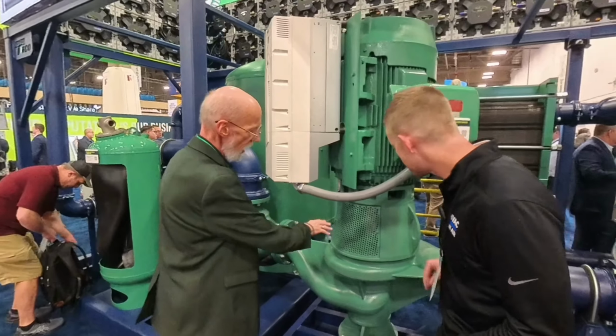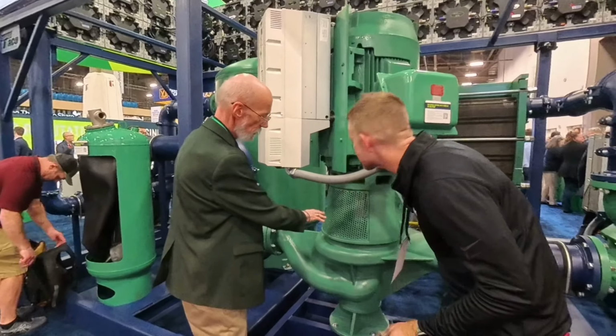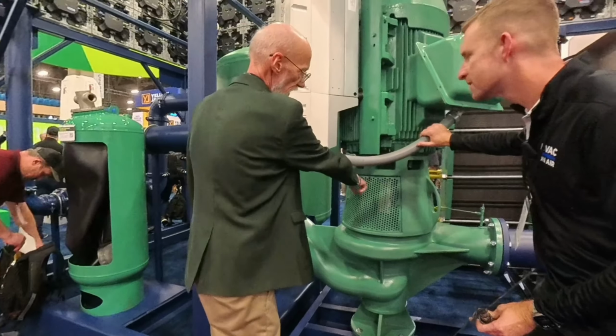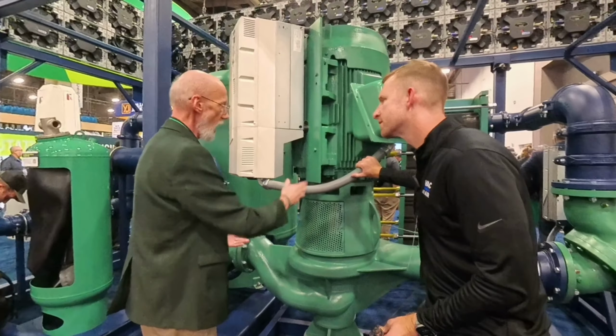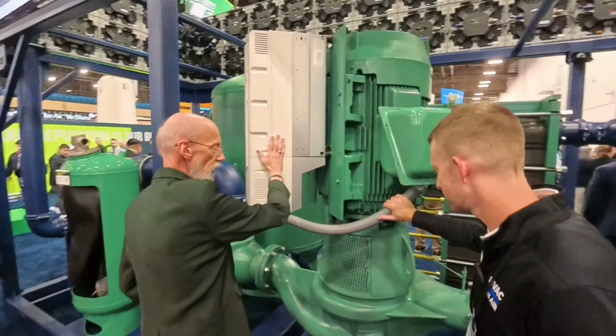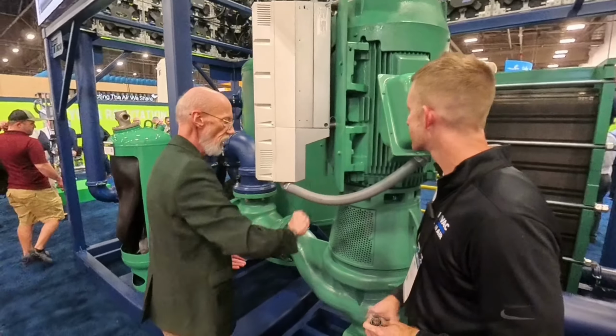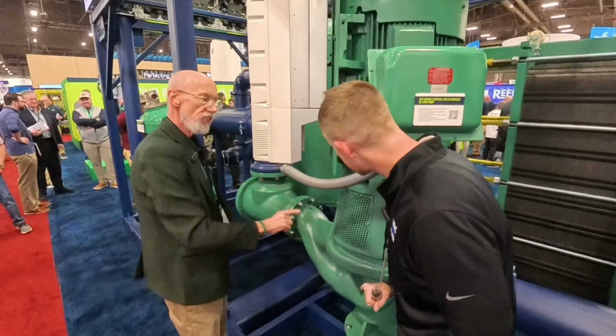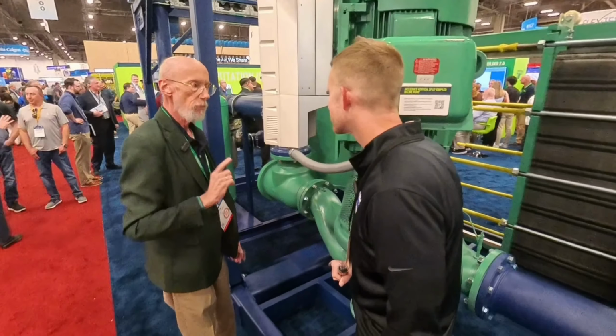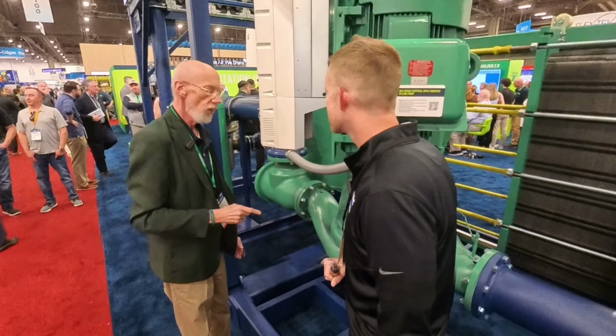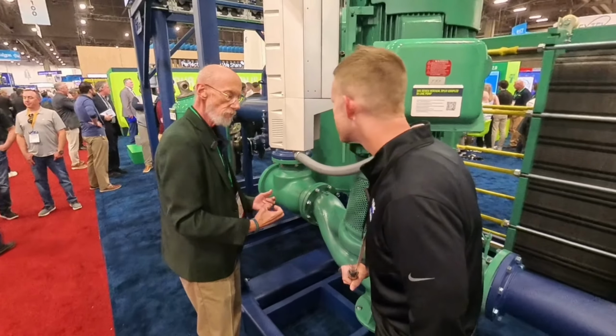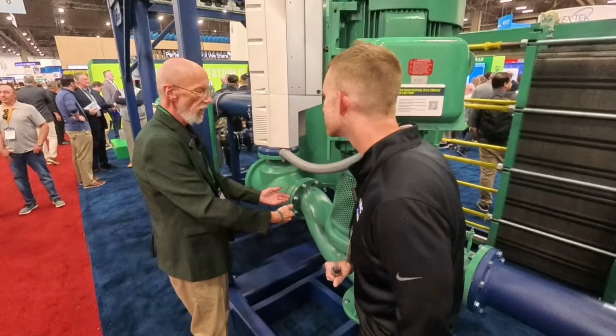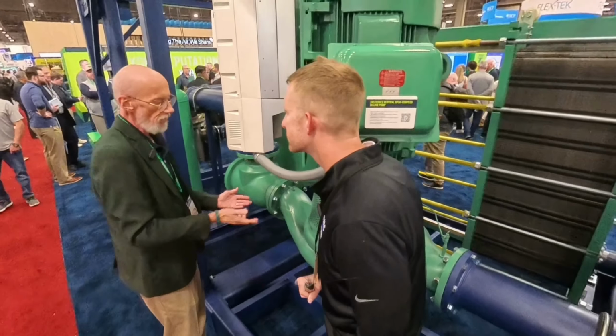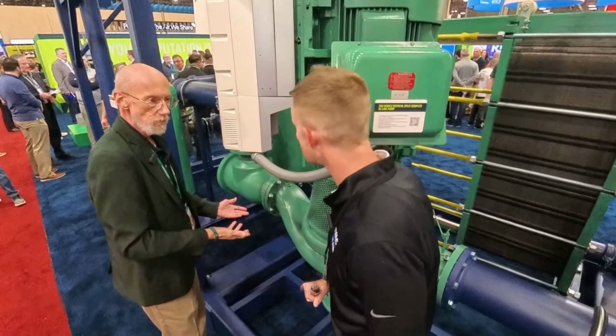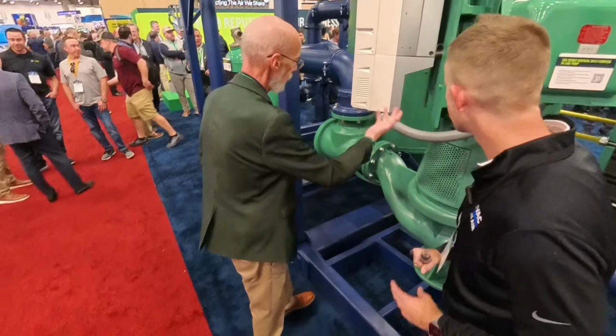So if I have a problem with the shaft seal on this pump, all I do is take this outer cover off, take the coupling halves apart. I never have to touch the motor. I never have to touch the drive or the electrical connections. I can change the shaft seal, which is the single most common failure point on a vertical inline pump. All I have to do is take this apart, change the shaft seal, put it back together again, and I'm back up and done. The heaviest thing I'm going to lift is about 5 pounds. Okay, so that's a vertical inline.